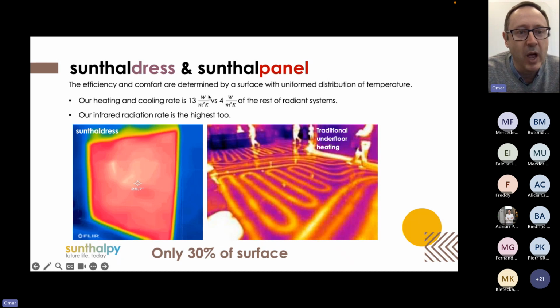A traditional radiant floor has a heat transfer coefficient of 4, while we have a higher coefficient of 13. We are more than 3 times more efficient than a traditional radiant floor for heating, and way more efficient for cooling, as we'll see later. Basically we only need 30% of the surface to achieve something equivalent.